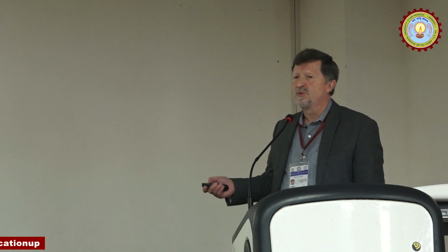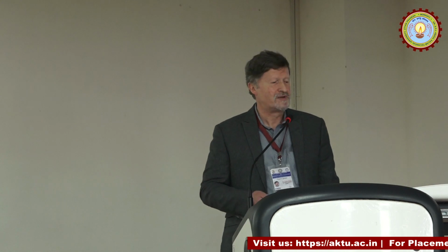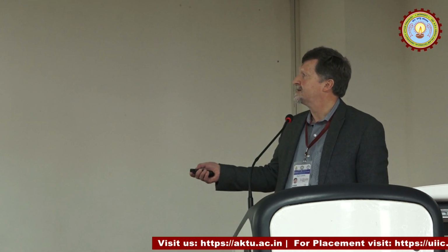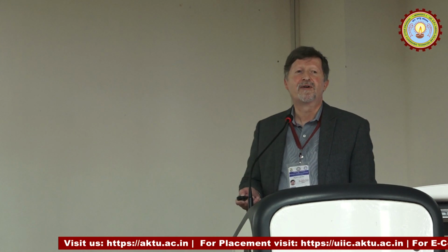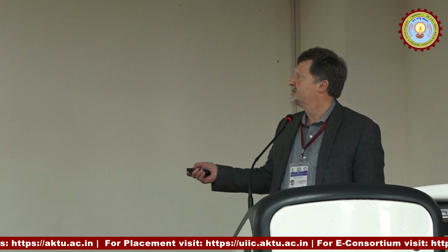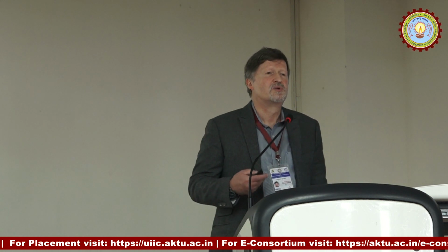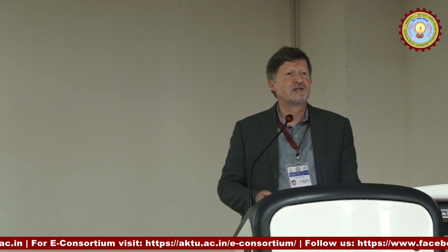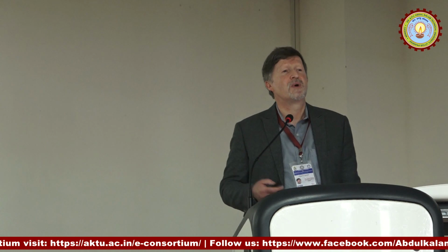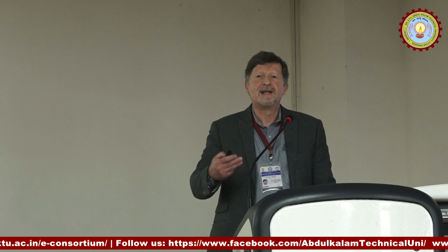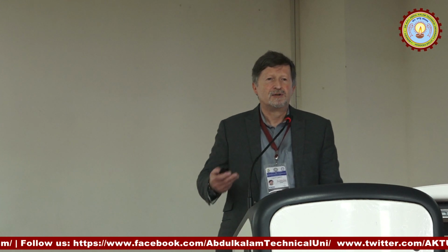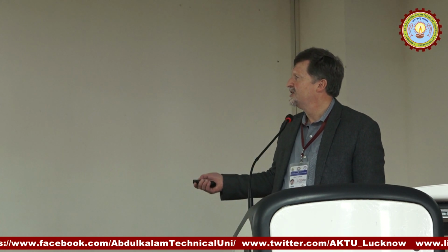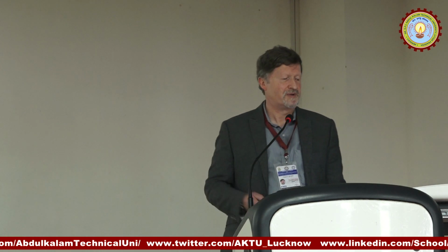Some of the challenges we face is we have to maximize the coupling of the microwave power into the breast tissue. The skin is the greater reflector of the microwaves, and so we have to overcome that. We are looking at various different electrical properties of our tissues, and here you can see the high permittivity and conductivity associated with the tumor is what gives us the contrast that we're hoping for. We also have to look at our losses within the tissue, particularly at the higher frequencies where there's greater losses. But once we get inside the skin, there's also challenges associated with those attenuations that's taking place and the power drop-off as a function of distance.